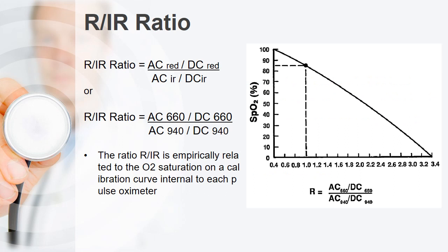The R to IR ratio — red to infrared ratio — is the ratio of the AC and DC current of the red light to the AC and DC current of the infrared light. This ratio is empirically related to oxygen saturation on an internal calibration curve specific to each pulse oximeter. On the calibration graph, at an R:IR ratio of 0.4, SpO2 is 100%, and the critical value is that when R:IR ratio equals 1, SpO2 is approximately 85%.